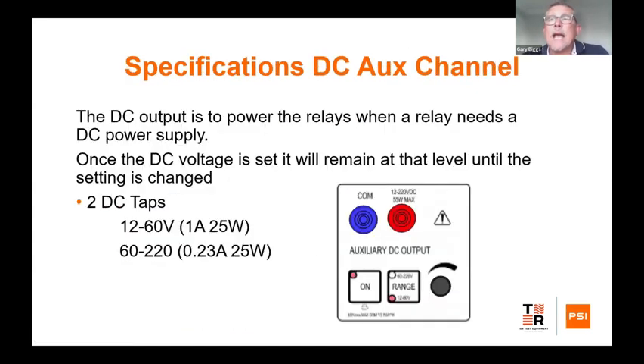We also have a DC output built into our relay test sets, and the DC output is effectively replacing the substation batteries. When I first started testing many years ago, if you went into a substation and tested a relay, you would normally connect up to the substation batteries. That's not been seen as recommended practice for quite a while. So now we've built in a DC voltage, and we can adjust that voltage and give you anywhere from 12 to 220 volts DC, which is capable of powering up relays that need an auxiliary power supply, such as the digital relays, or an older transistor type relay where you need to power it up to test the relay.